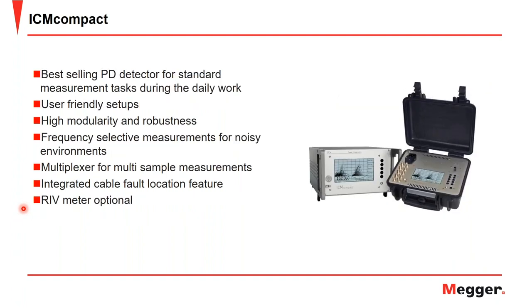Next, we have the ICM Compact, which is a more popular detector for standard measurement tasks during daily work. It has user-friendly setups. Again, it offers high modularity and robustness. Frequency selective measurement for noisy environments. If you're trying to avoid some high-frequency noise, you can select your measurement frequency. It offers a multiplexer for multi-sample measurements, as well as an integrated cable fault location feature, and even a radio interference voltage meter, or RIV meter, is optional with the ICM Compact.